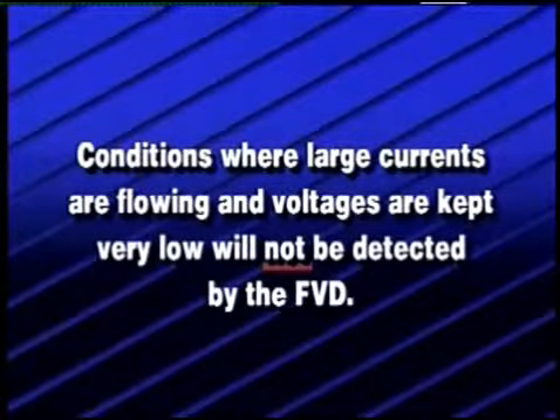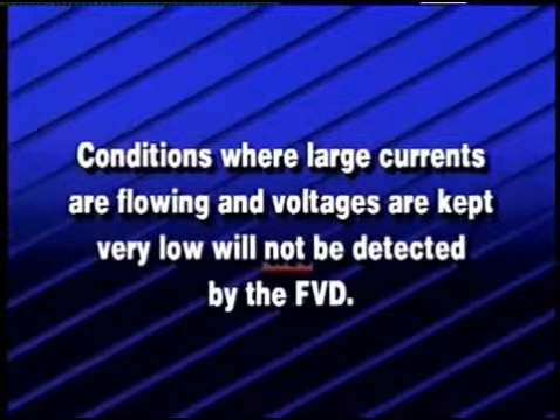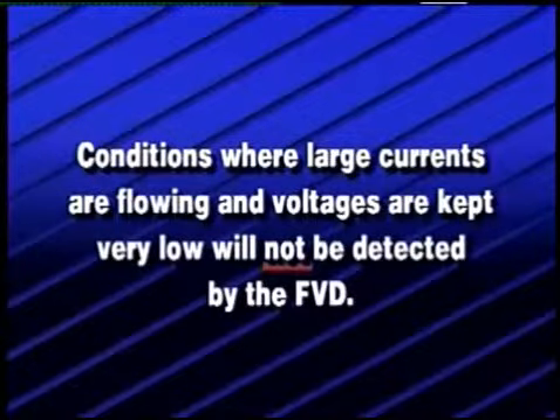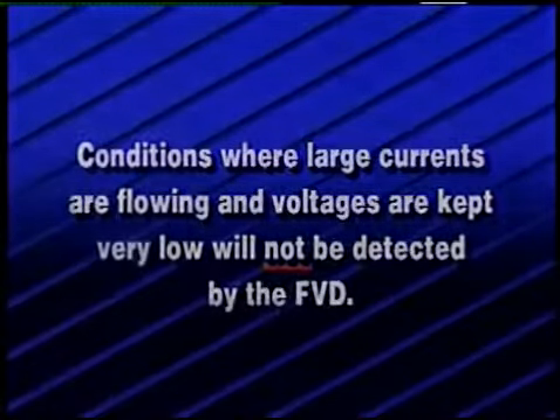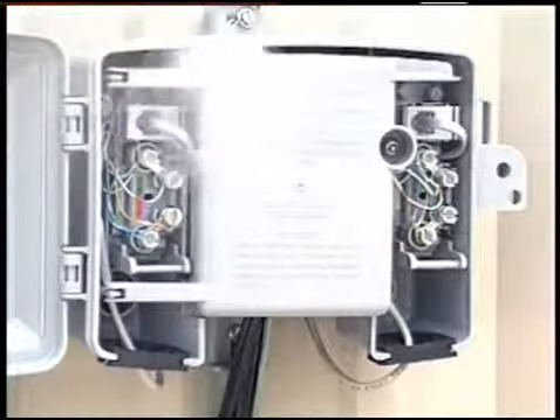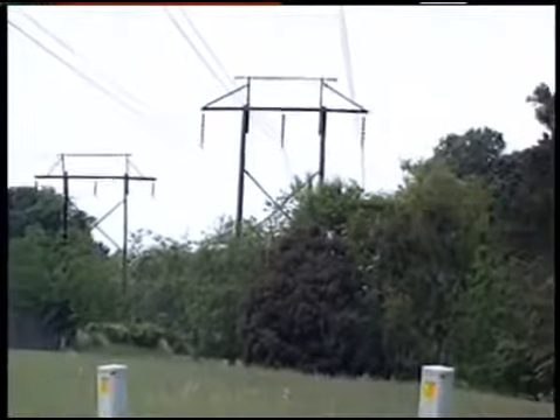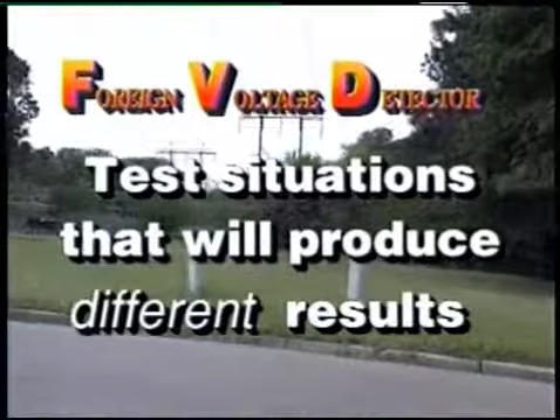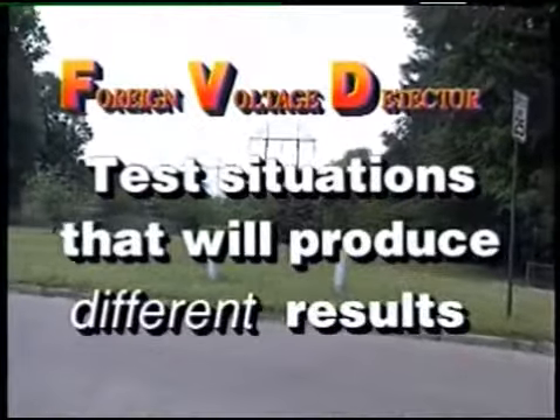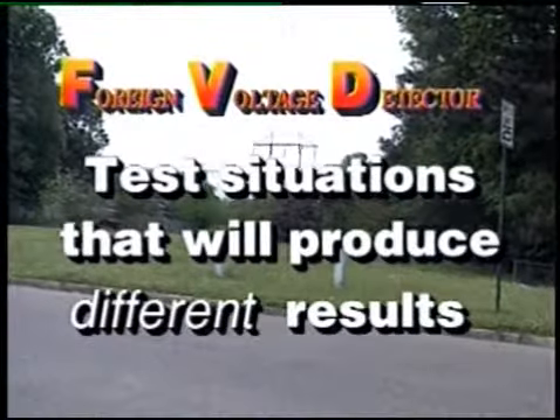The F.V.D. can detect voltage only. This means that conditions where large currents are flowing and voltages are kept very low will not be detected by the F.V.D. Always look for indications of high current, such as discoloration, excessive heat, smoke, etc. Always follow your company's safety policy when placing or removing temporary or permanent bonds while dealing with potential high current situations. Because the F.V.D. is a remote sensing device, there are some testing situations that will produce different results. The situations require procedures that may be unusual or new to you.